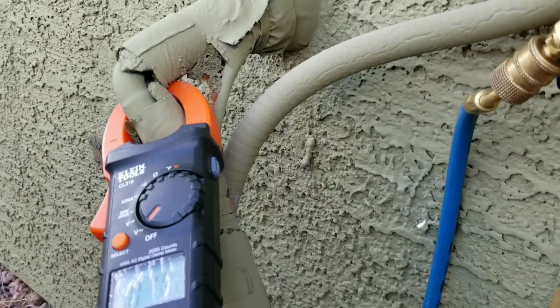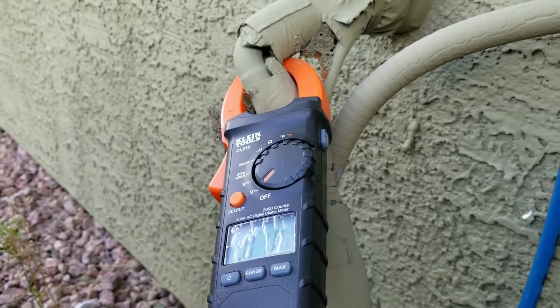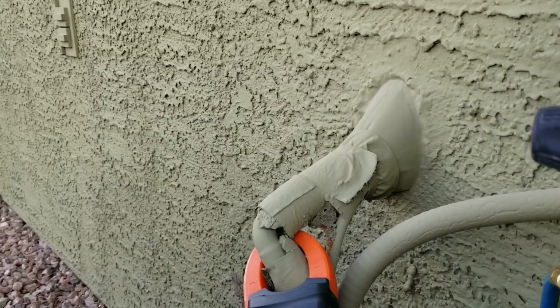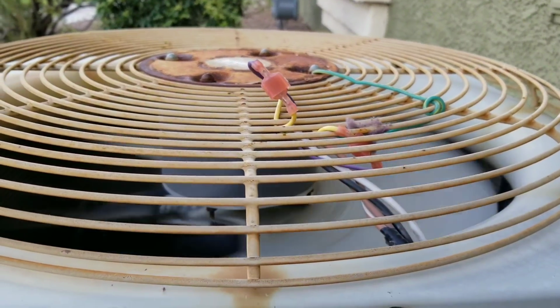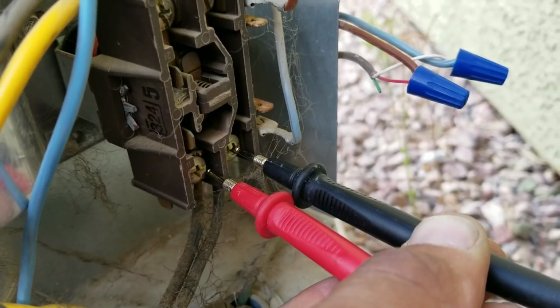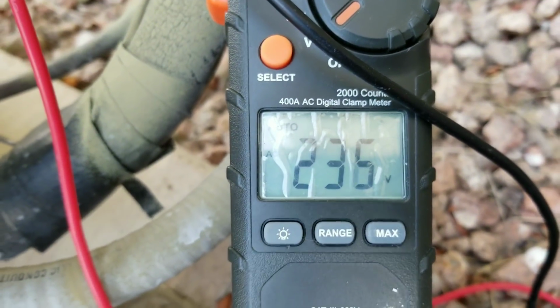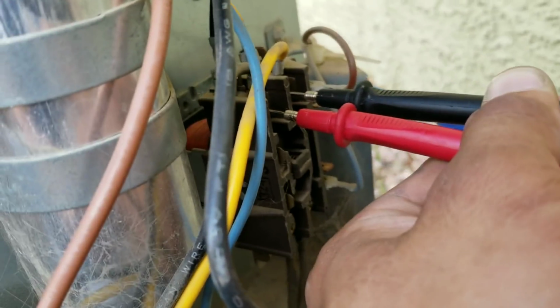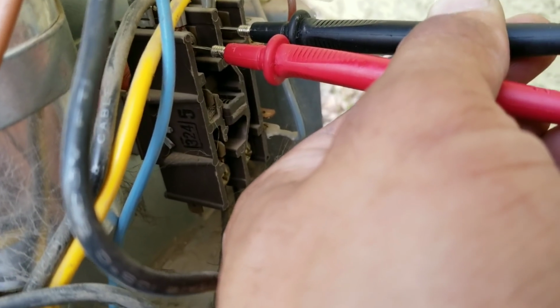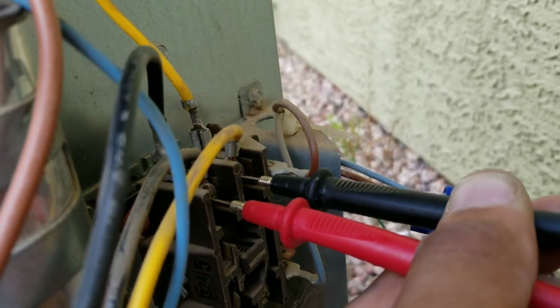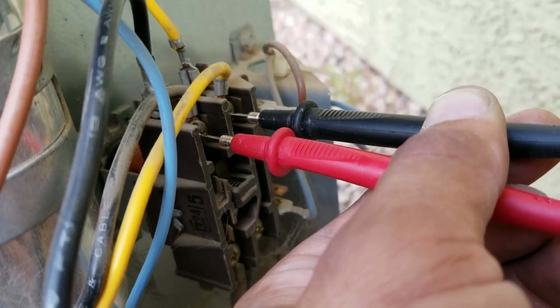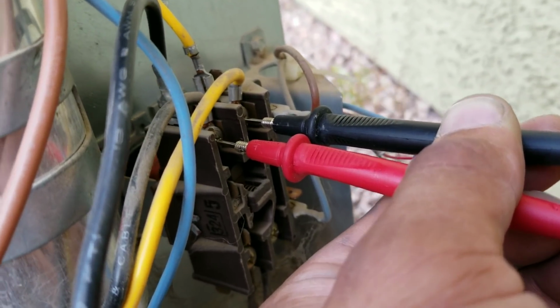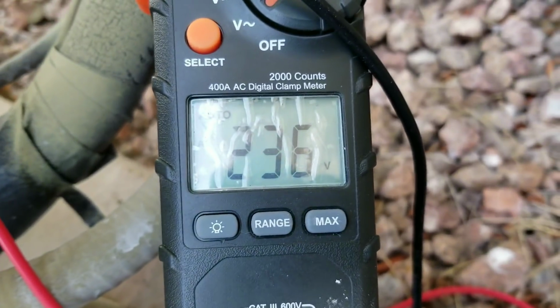I'm going to plug my disconnect back in, and I'm going to take my high voltage reading on my contactor. As you can see here, again my fan motor turned on. The bottom of my contactor is my incoming voltage coming from my disconnect, and right now I have 240 volts. Here my contactor is engaged. That's telling me that it is calling for cool, and I have my leads going to the top of the contactor, which sends power to my compressor, and here I have 240 volts.